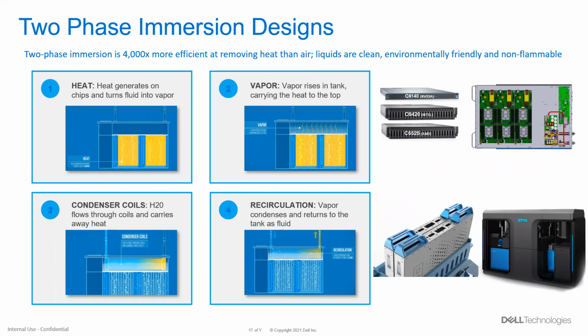Two-phase immersion is a slightly more advanced capability where the fluid that the IT is immersed in actually has an engineered boiling point that allows for the fluid, when it comes in contact with a hot component such as the CPU, to boil off. That vapor rises to the top of the sealed tank and hits a condenser unit, which converts it from vapor back to a liquid, and that liquid then will fall back into the tank. So there's a circulation of the fluid to vapor back to the fluid that naturally causes a movement in that fluid. So you don't need any pumps to move this engineered fluid around.